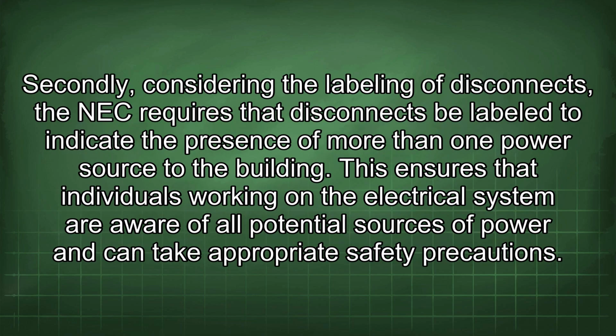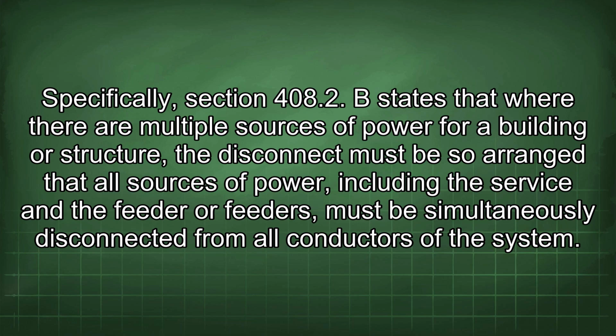Secondly, considering the labeling of disconnects, the NEC requires that disconnects be labeled to indicate the presence of more than one power source to the building. This ensures that individuals working on the electrical system are aware of all potential sources of power and can take appropriate safety precautions.